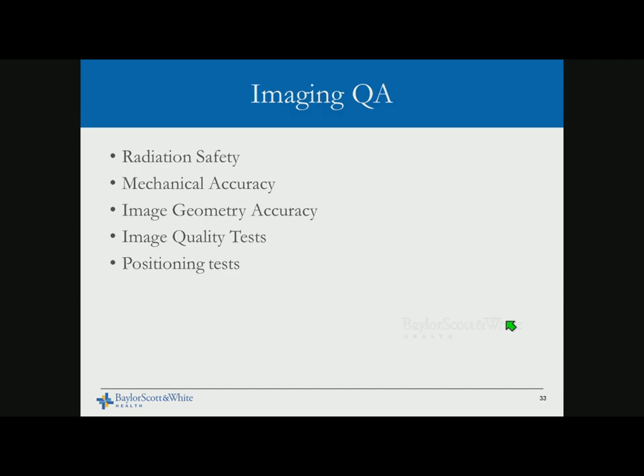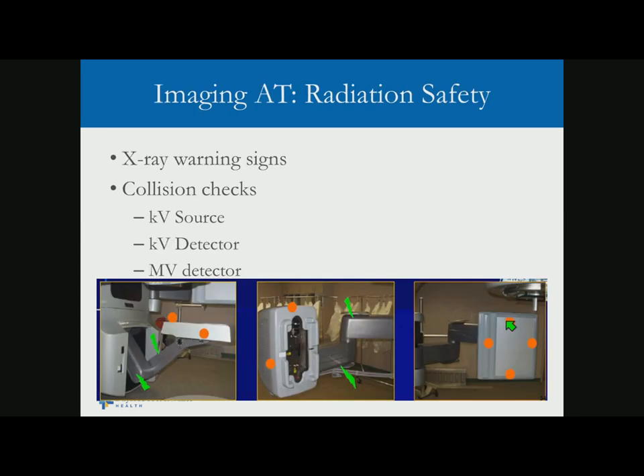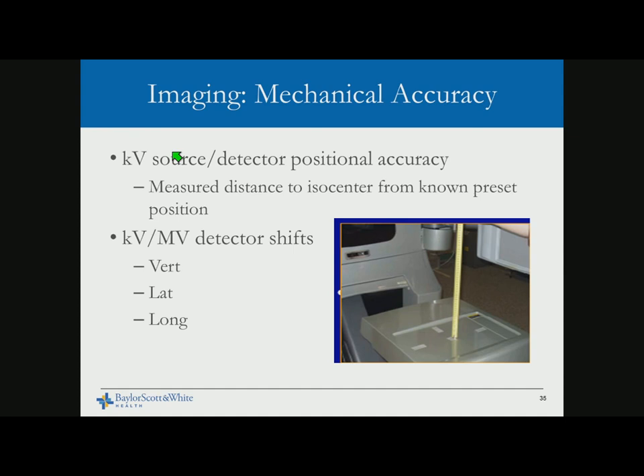Imaging QA is now part of all LINAC acceptance testing. We need to test KV source interlocks — if there is a collision it needs to stop — and MV source, MV detector, and KV detector collision checks, along with X-ray warning signs. Mechanical accuracy of KV source and detector positional accuracy are important: if the detector is in a different location and you use a digital graticule, you won't have the right magnification. It's critical to test detector position and measure from the isocenter.